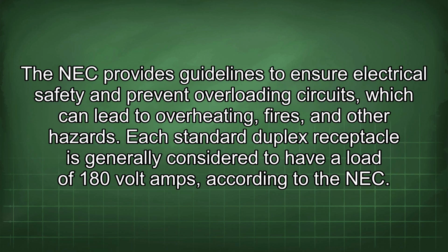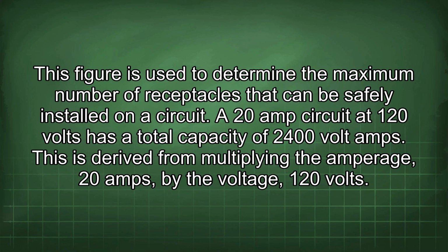The NEC provides guidelines to ensure electrical safety and prevent overloading circuits, which can lead to overheating, fires, and other hazards. Each standard duplex receptacle is generally considered to have a load of 180 volt amps according to the NEC. This figure is used to determine the maximum number of receptacles that can be safely installed on a circuit.